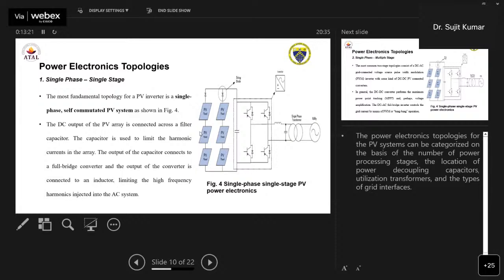Now let's look at the Power Electronics topologies available to us. The first topology is single phase, single stage. These PV system topologies can be categorized on the basis of the number of power processing stages, the location of power decoupling capacitors and utilization transformers, and the type of grid interface. The most fundamental topology for the PV inverter is the single phase self-commutated PV system.